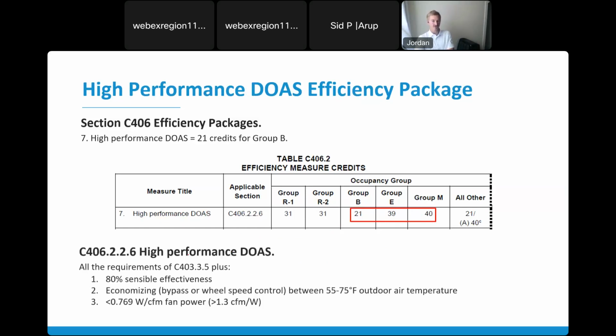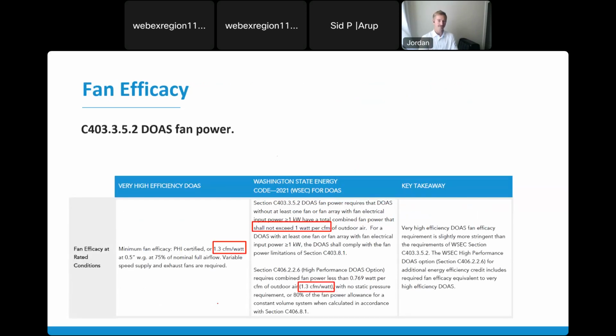What are all those requirements? It's all the basic requirements of C403.3.5, that's the DOAS section. But it adds, as I mentioned, 80% sensible effectiveness instead of 68. It requires economizing, so this is just bypassing the wheel or heat exchanger between 55 and 75 to provide airside economizing. And then a little bit more strict fan power: less than 0.769 watts per CFM, or greater than 1.3 CFM per watt.